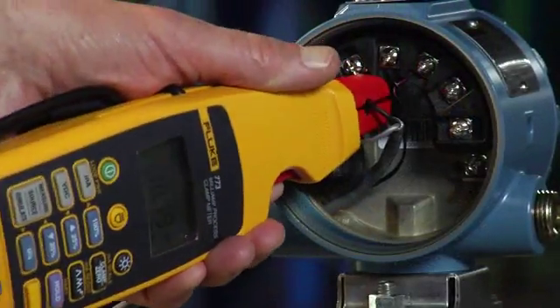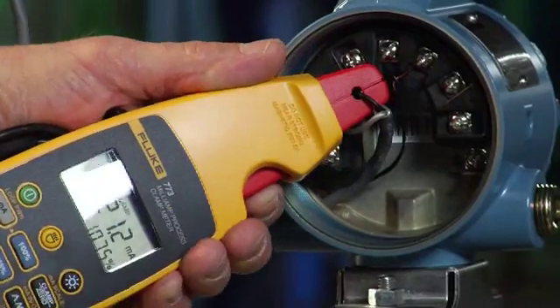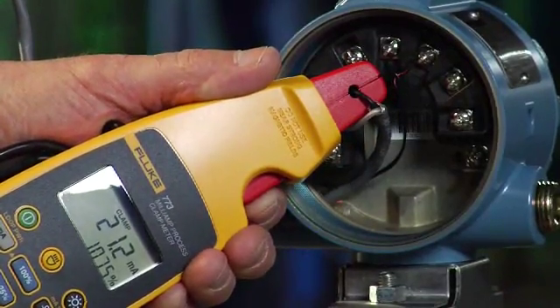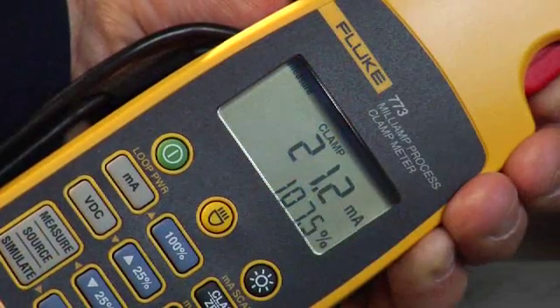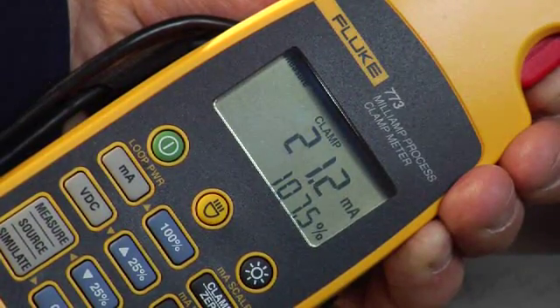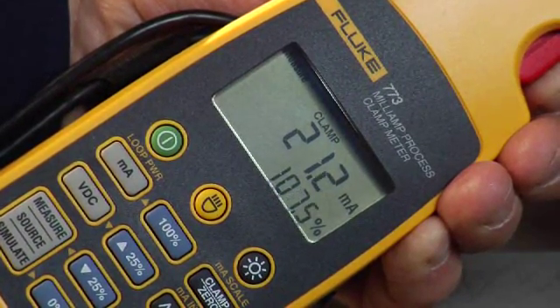First, clip the Fluke 773 onto one of the milliamp signal wires to make the measurement. An indication of 21 milliamp shows that indeed the loop is in alarm and that further troubleshooting is required.